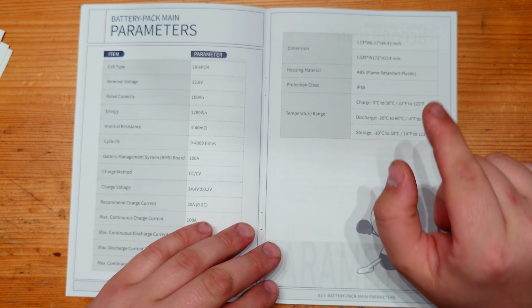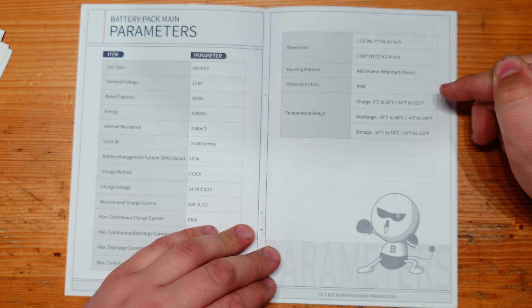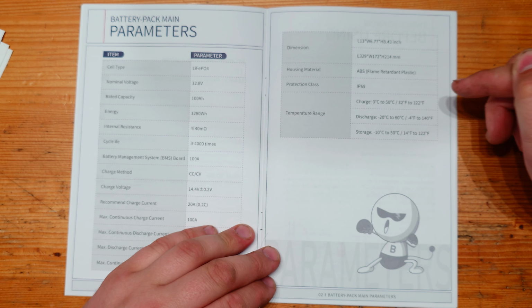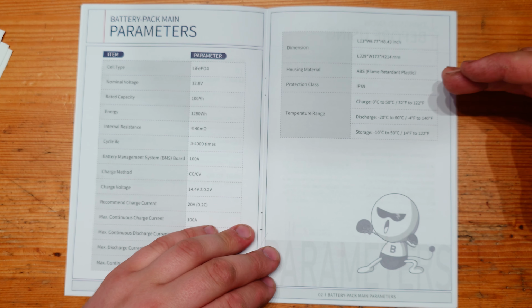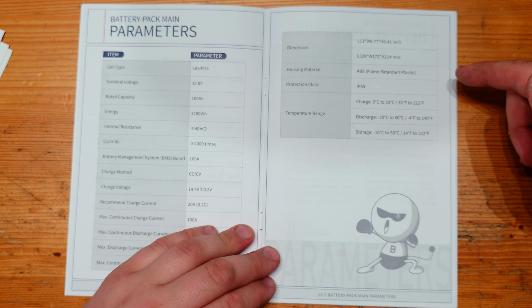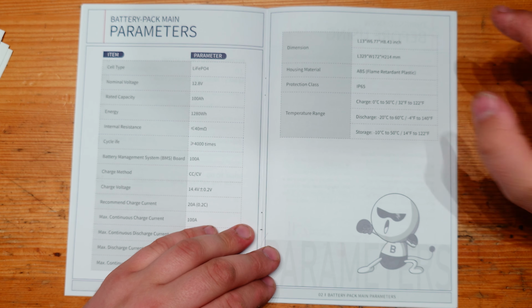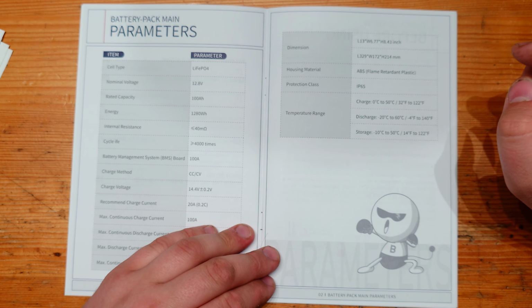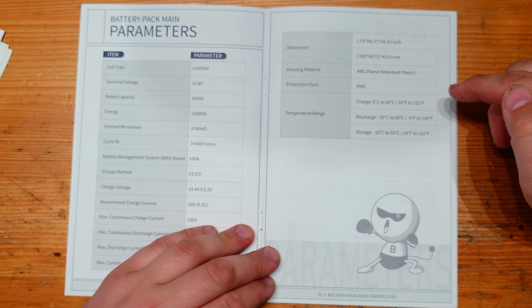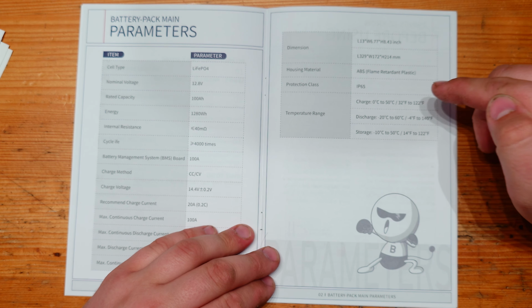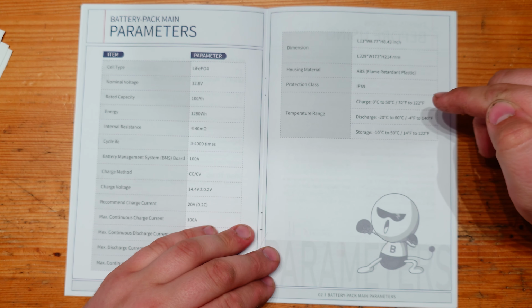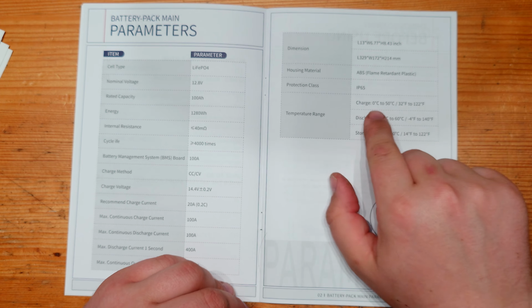It makes sense that they write some temp ranges here and separate charging and discharging. My advice would be to charge it between 5 and 30 degrees Celsius to prevent higher damage to the battery, and only charge outside of this range when you push small currents. Never ever shall you charge outside of the claimed range - you would destroy the cells below 0 degrees Celsius. So it's good they wrote it here.